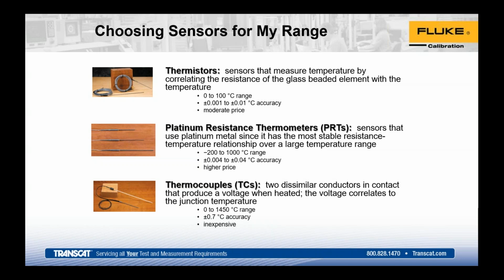Then we move into the really high temp stuff, which is usually TCs. Most PRTs are limited to about 400 to 500°C. We do have a few models that can take heat up to about 660, and I've even got one that'll go to 1,000. But once you range outside of that, you have to go back to thermocouples. Where thermistors have very high accuracy but very small range, as you give up some of that range, or need more range, you lose some accuracy - and that's just due to the physics of things. When things are exposed to such high temperatures, cooling and heating, if we get into the weeds, the crystals of the metal are moving so quickly and changing states. That's where you see drift across the different types of probes and sensors.